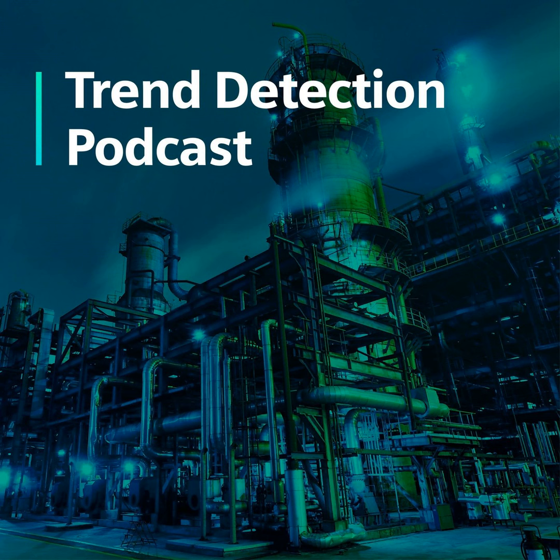But you may also look at drive data. So if you've got variable speed drives or controlled by PLCs, etc., you can get a lot of metrics from your drives, or even your PID control loops, or timings of actions. So if you've got actuators that move from point A to point B, the time can be really useful if it's an open loop control, etc. I could go into a lot of detail about this. But fundamentally, we're looking for data, and the technology is generally sensors or connected IoT devices.